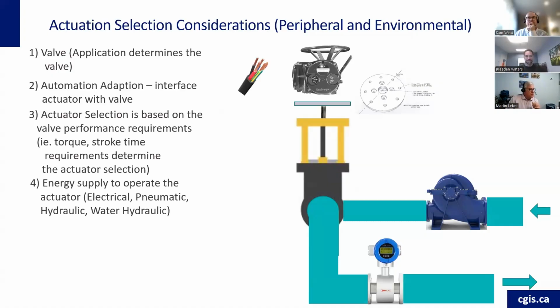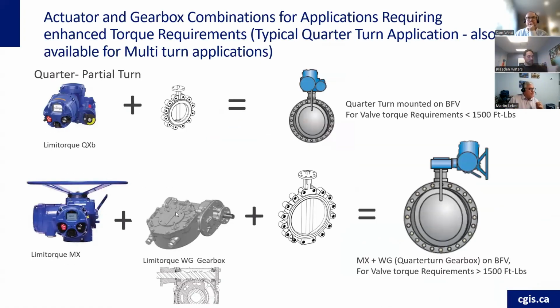So we talked about the actuator selection considerations, and just a side note here, there are all different ways of cobbling up actuators with gearboxes to increase your torque. This is just one example, a quarter turn example, but for the multi-turn, it's no different. You can put an actuator with a gearbox to increase your torque. But keep in mind that when you do that, your torque is increased, but your stroke time is also increased, because there's a reduction in the actuator RPM at the output of the gearbox. So you weigh that, and there are all different ways of sizing those actuators to fit the application.